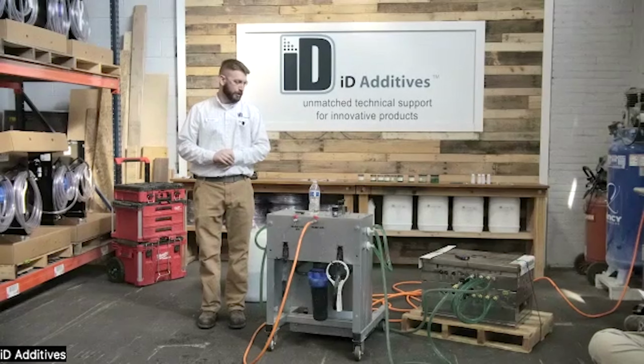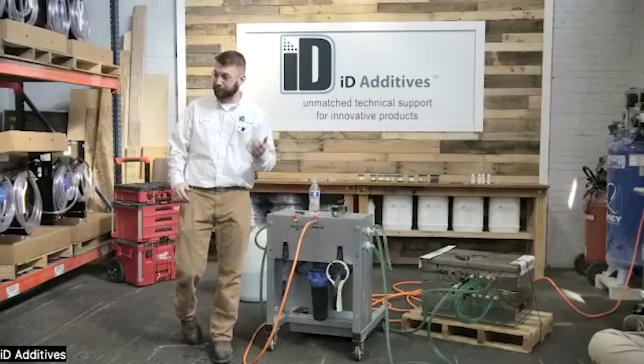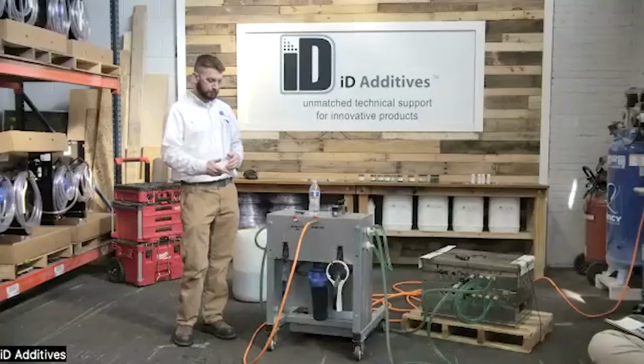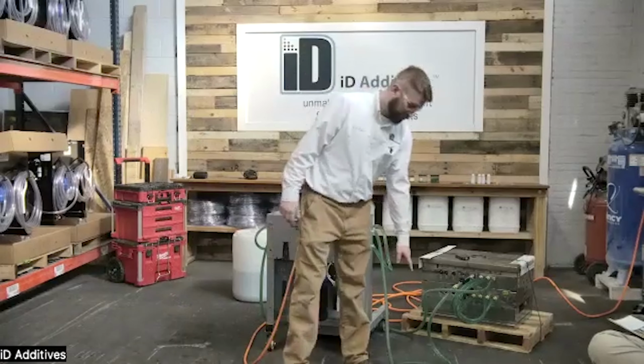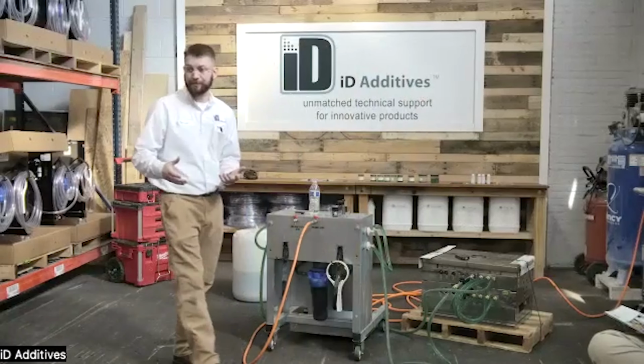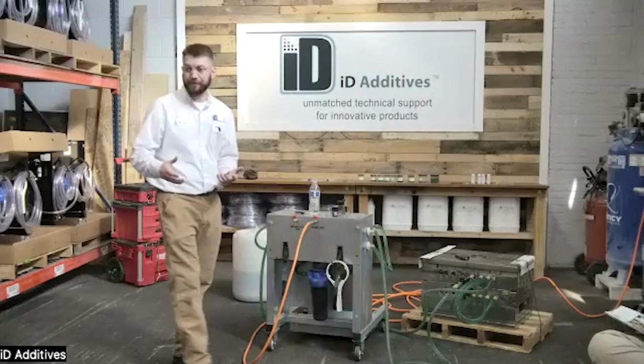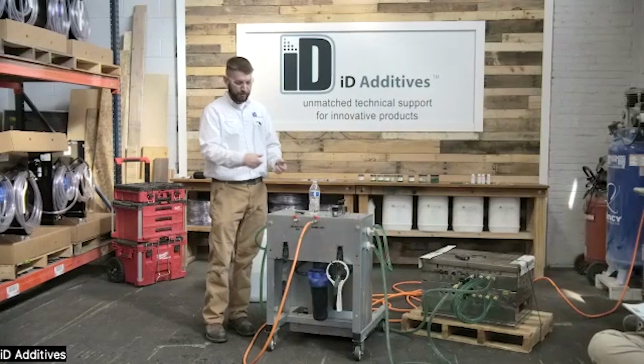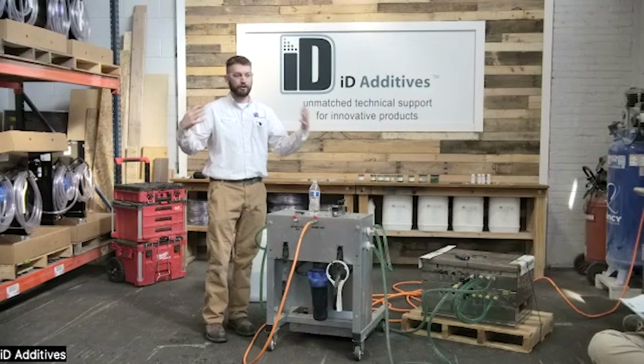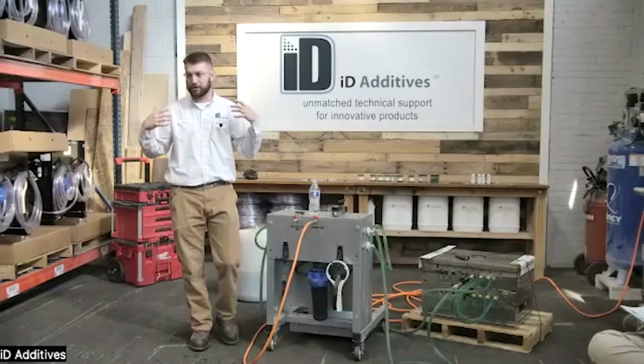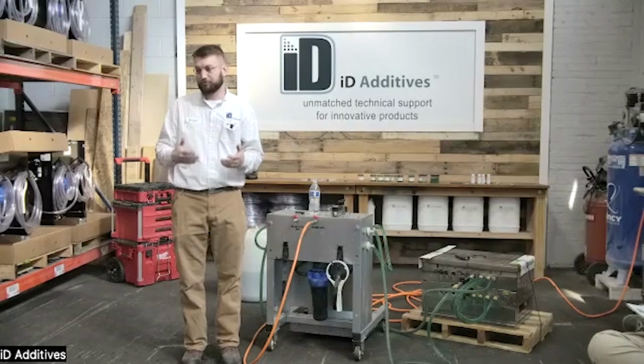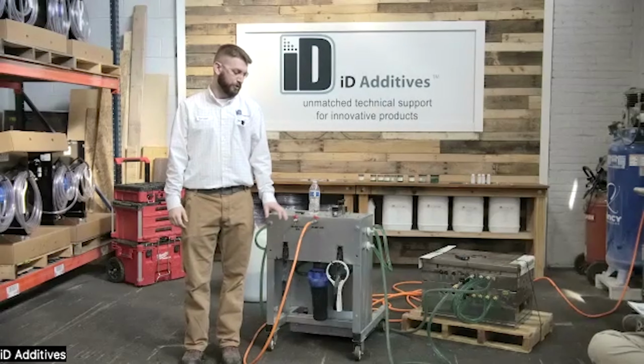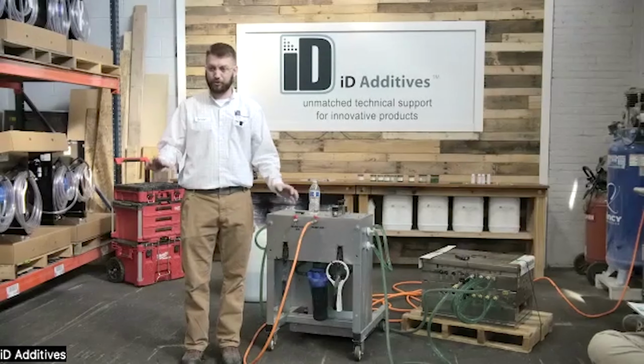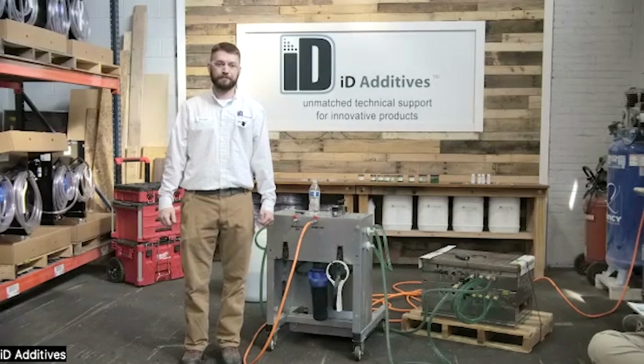What I like about doing all these different pieces of equipment - maybe your Thermolator is right at the press. If you know that Thermolator and the copper lines plug up every 18 months, or your heat exchanger plugs up every 16 months, I tell people to plumb in some shut-off valves with quick connects right in line. So if it's every 18 months, say every 12 months I'm going to shut off my water supply, plug this in for an hour, let it circulate, keep it clean. You're not having your maintenance team spend extra time pulling the heat exchanger off - you're only dedicating an hour once a year to prevent that. So I always tell people, if you can connect to it with quick fittings, you'll make your life easier down the road. But good question.